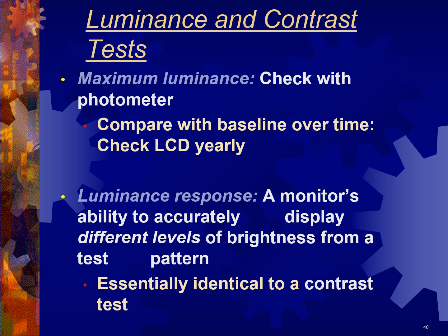Now, the plus or minus 5% is not for the photometer, that's for the luminance response. So you test this when you first set it up, and you set the brightness and contrast level, you test that it's in the appropriate DICOM range, and then you come back and confirm that it's maintained its brightness and contrast over the course of the year, within plus or minus 5% agreement of what you measured last year, 5% of historic and baseline testing, okay?